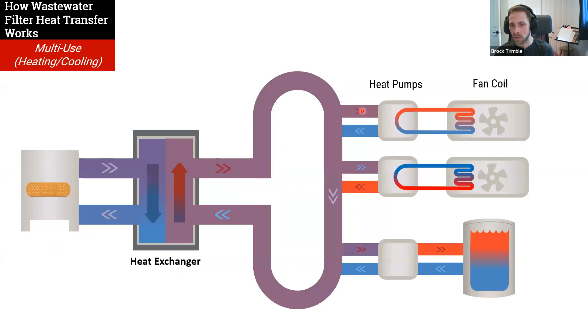With that setup you'd have opportunities for both energy recovery and energy rejection—building heating and cooling, sending energy out into the load, similar to the energy sharing application. You'd use the SHARC to supplement and support the geothermal field if it starts to overheat or overcool, by sending energy into or out of the loop using the sewer source as an energy source or heat sink.